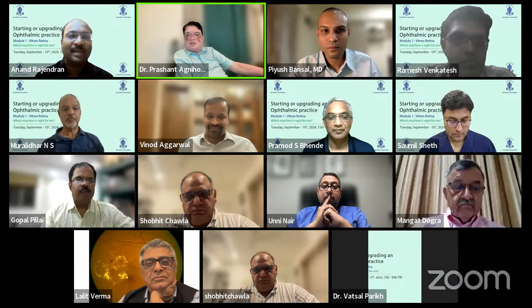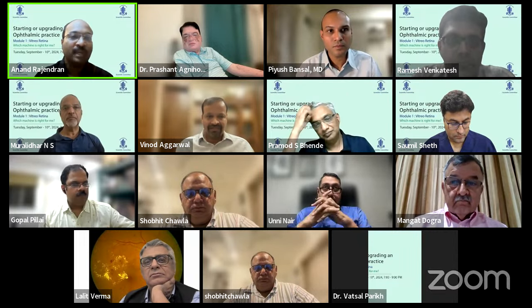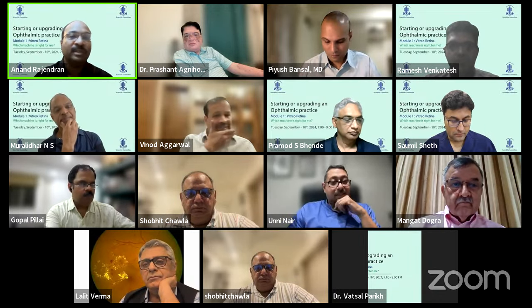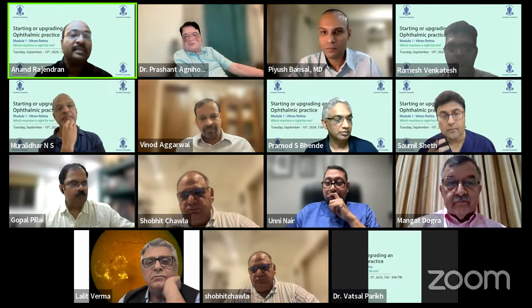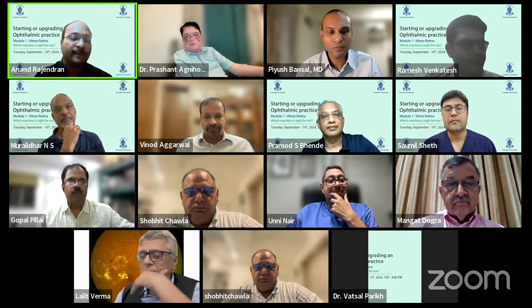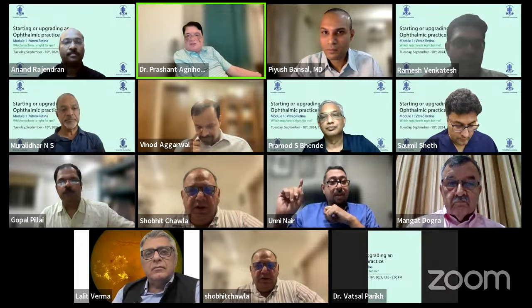If I could add one quick comment. Another parameter that can be looked at is whether certain machines are upgradable. For example, in the Spectralis itself, you have a wide range. He briefly mentioned that. So if you're investing in a lower-end or mid-range Spectralis device, see if it can be upgraded as part of your contract or as part of the machine. Other things he also mentioned: for a high volume setup, it's important to see whether you can get a good number of licenses, and whether it integrates with your EMR platform or if there is a viewing platform, because you might have multiple stations or settings, and whether this is accessible at different points. Yeah, I think that's very important. You have to have integration between the different machines, and only then can you integrate your data.